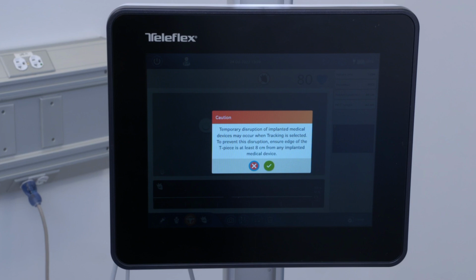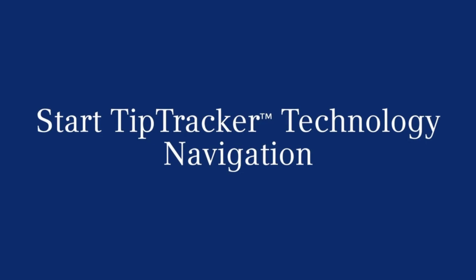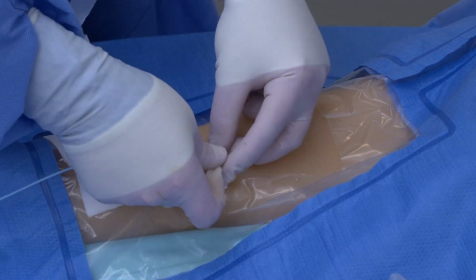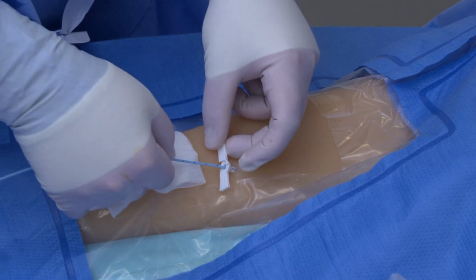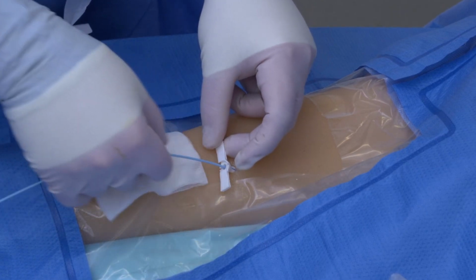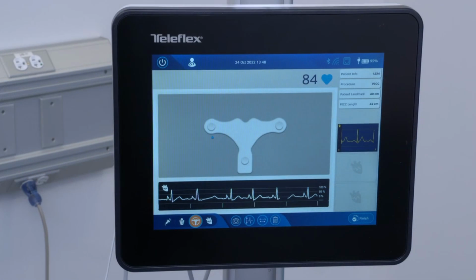The VPS Rhythm DLX device can still be used on patients with implanted medical devices, although another method of tip confirmation is required. To ensure patient safety, review the EMI warning and select either the green check to continue or the red X to not engage navigation mode. Slowly thread the PICC per institutional policy and procedure and manufacturer's instructions for use.